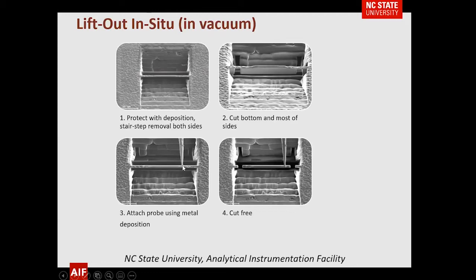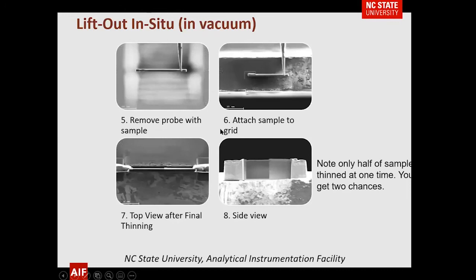We cut it away completely, move the grid into place, and attach the section to it. In this particular approach, we attach it directly to the top of the grid and then thin part of it. Why only part? One reason is you've done a lot of work — it's easy to go too far and lose your area of interest. By thinning only part, you have two tries if needed. It also provides stability: if you thin too large an area at once, warping can occur.